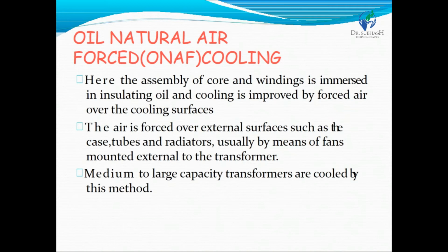In this method, the transfer of the heat from various parts of the transformer takes place naturally, as explained for the ONAN type cooling. However, the hot oil is now cooled by means of fans mounted near the transformer, as shown in the next slide.